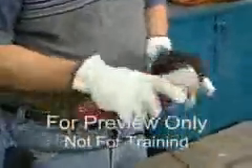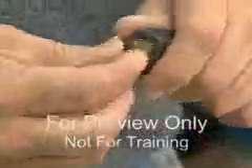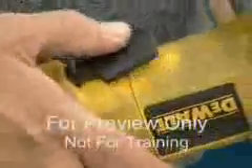Check the body of electric tools for cracks or other damage. Check that power cords are not frayed and that plugs do not have loose or broken prongs. Check whether the tool's power switch can be locked in the on position or automatically shuts power off when the trigger is released. The switch should operate freely without sticking.